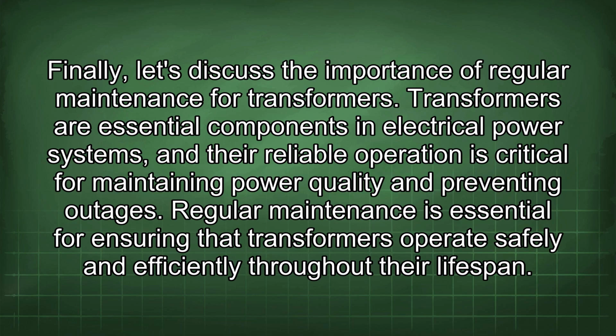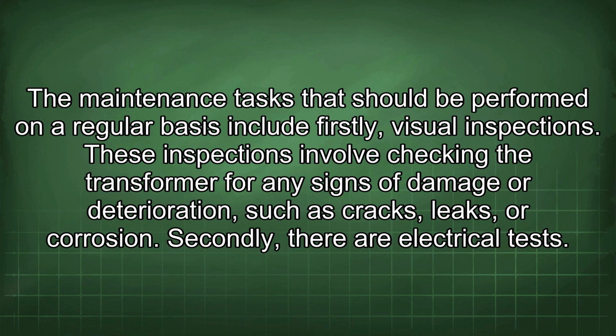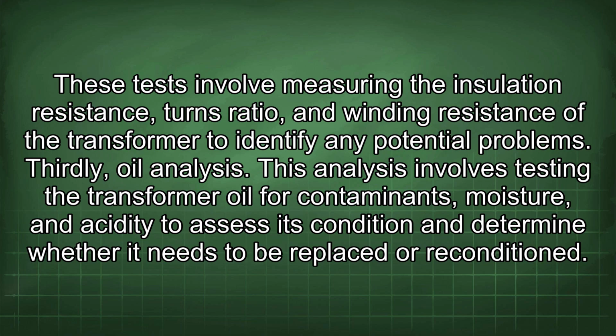Transformers are essential components in electrical power systems, and their reliable operation is critical for maintaining power quality and preventing outages. Regular maintenance is essential for ensuring that transformers operate safely and efficiently throughout their lifespan. The maintenance tasks that should be performed on a regular basis include, firstly, visual inspections. These inspections involve checking the transformer for any signs of damage or deterioration, such as cracks, leaks, or corrosion. Secondly, there are electrical tests. These tests involve measuring the insulation resistance, turns ratio, and winding resistance of the transformer to identify any potential problems. Thirdly, oil analysis. This analysis involves testing the transformer oil for contaminants, moisture, and acidity to assess its condition and determine whether it needs to be replaced or reconditioned.